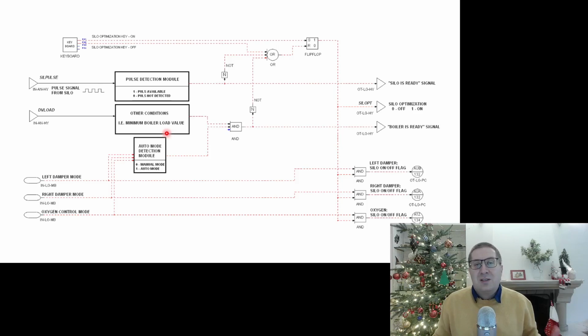Maybe this algorithm was trained and developed for normal process operation, not for startups. If we see there is a startup, let's say the load of the industrial process is rapidly increasing, then we can say, oh no, those are not conditions for the AI method. The AI method was not tested and not trained on those conditions, so we should turn it off.